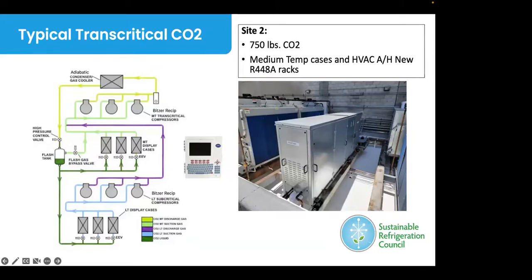So this got us in a position where, of all the cases that were being replaced, we were able to get them over to a natural refrigerant and also pick up the coolers. The medium temp stayed on an R448A. We put in a new R448A rack that picked up the existing medium temp cases and also the air conditioning in the store. Next one.